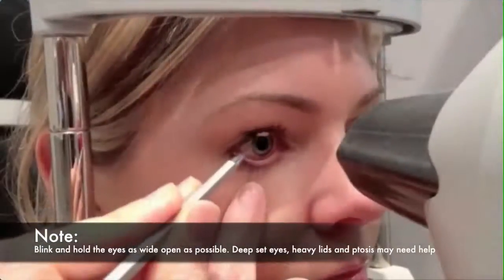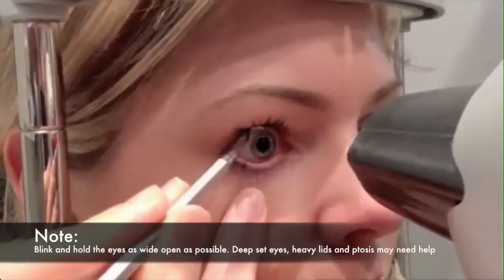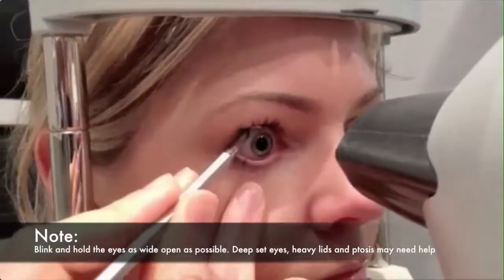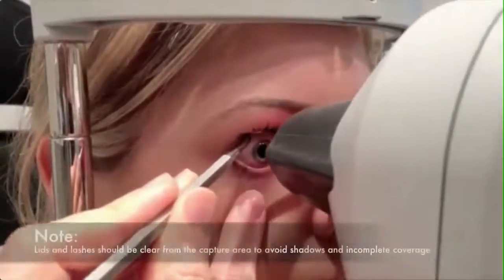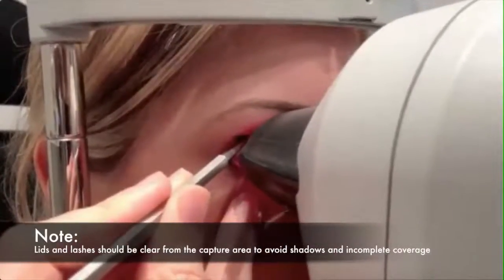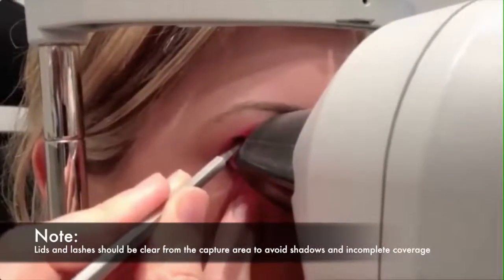It is also important to note that when the cone comes close to the cornea, the lid should be completely out of the way, so as to avoid decreased capture area and shadows of the Placido rings.